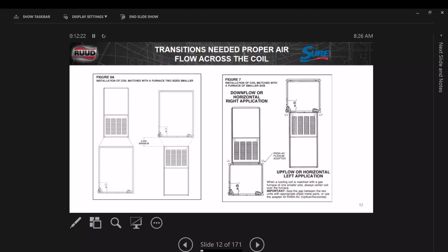Whenever you move air across these heat exchangers, you know they're tubular, and some of them are sitting sideways. The air takes a lot of turbulence in that plenum when we're going from the furnace to the coil. And then I've seen it to where the coil is pushed over to one side. Now, if you're using an A-coil in there, if you have it pushed over to one side, we miss a whole slab with that furnace. So that causes us to have low pressures.